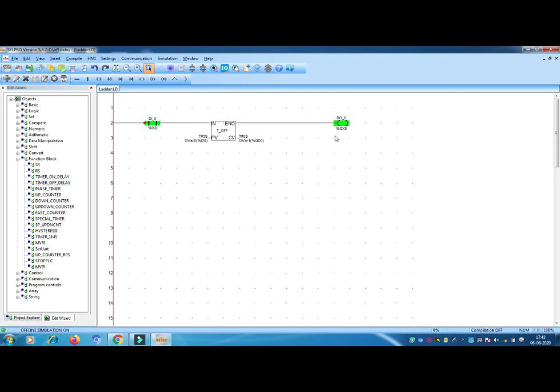What happened? Our motor is on, which means our timer is in on condition only, but it will not work unless we turn off the switch. Because the function of the off delay timer is that the timer works only after turning off. Let me give one example: when you are going home in a hurry, you have to turn off the switch compulsorily, but your production should run up to 10 seconds more.